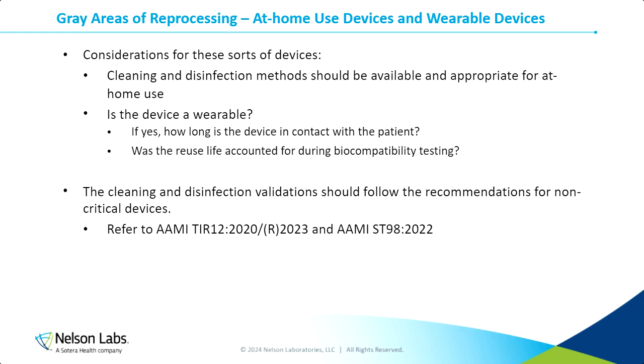You want to make sure that the cleaning and disinfection procedures are appropriate, and that they're not going to be extensive and require additional complicated materials or supplies. If your device is a wearable, you'll want to account for how long the device is in contact with the patient and how many times it's being reprocessed. Are there reprocessing residuals left on the device that are going to cause an issue in terms of biocompatibility as the patient wears it long term?